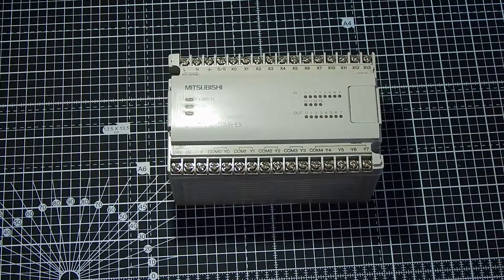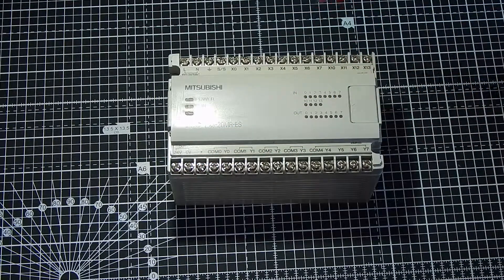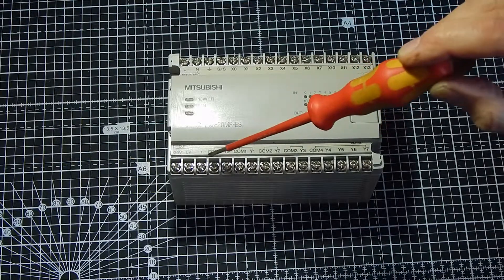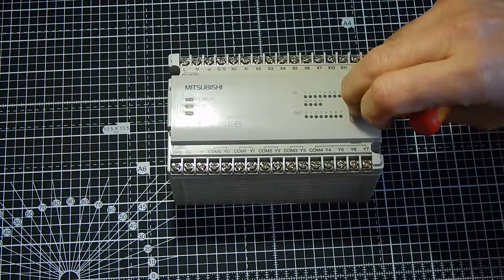Across the bottom, there's a 24-volt auxiliary output. That would be suitable for sensors and switches to the inputs, that kind of thing — not suitable to power relays and contactors, so you'd have another supply for that. And there are 8 relay outputs, just dry contacts. That will switch mains and will switch up to 5 amps, so it's a reasonably powerful unit and can do quite a bit.